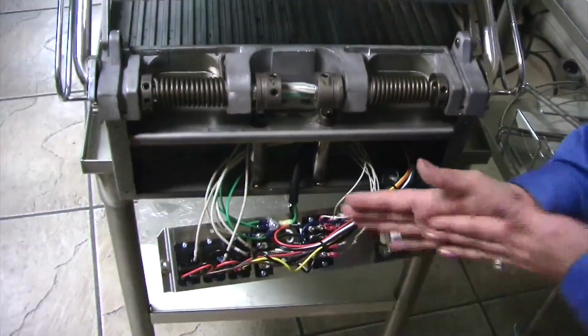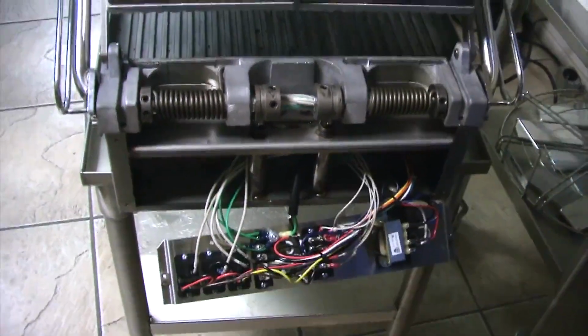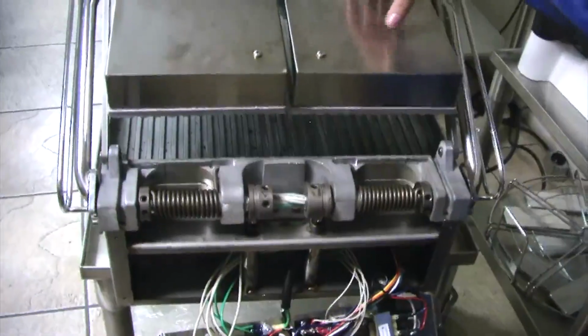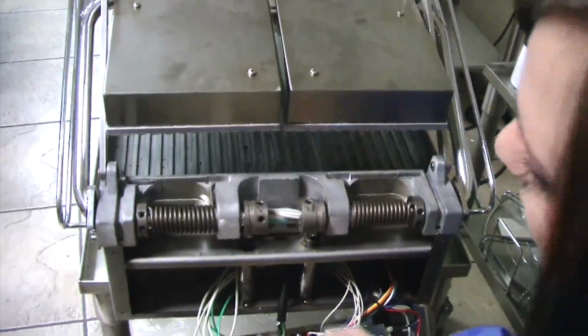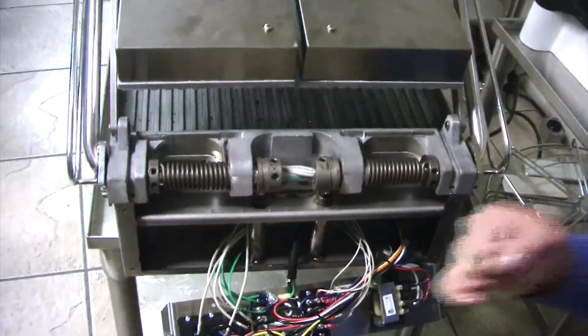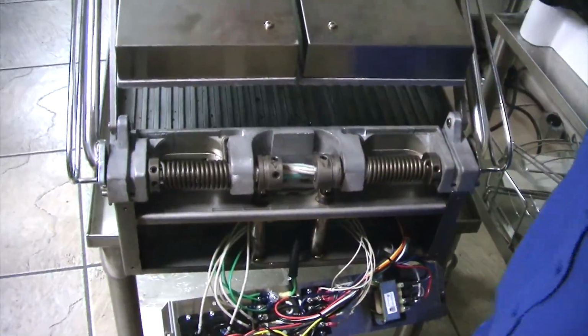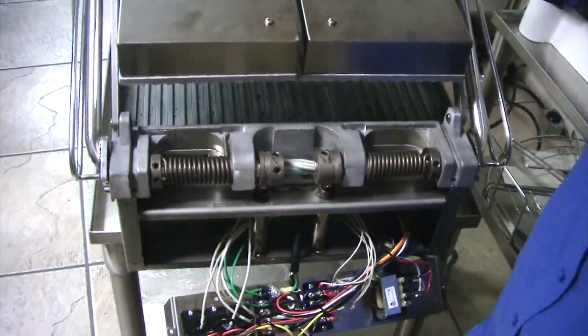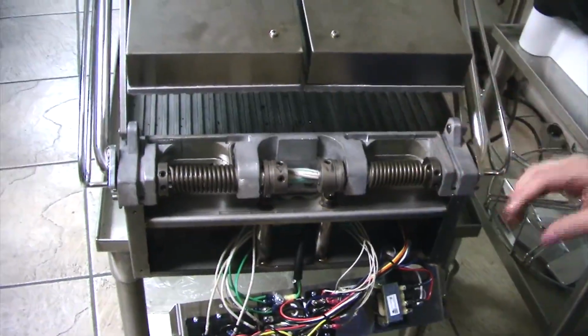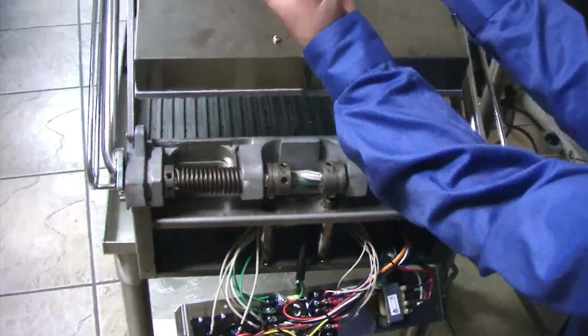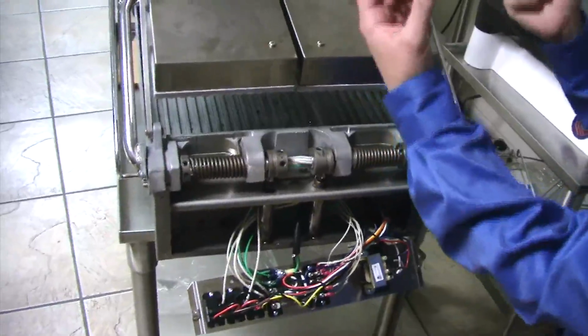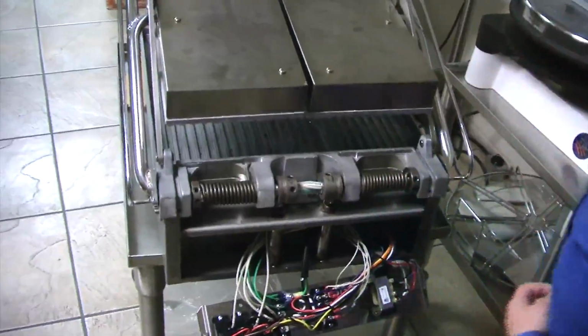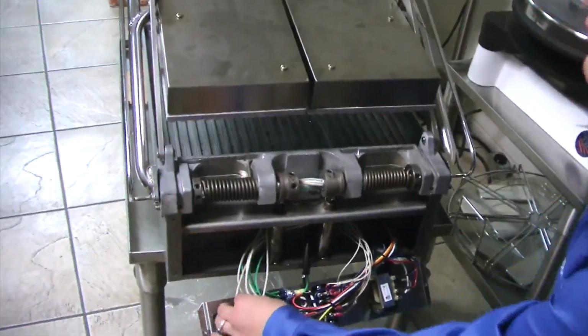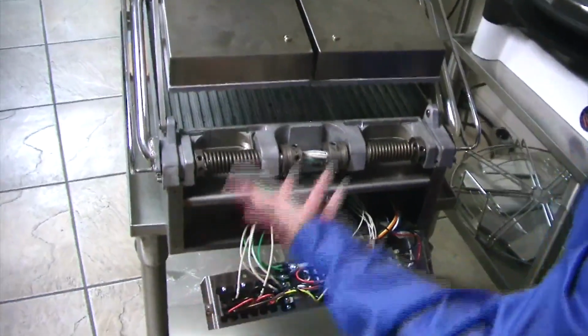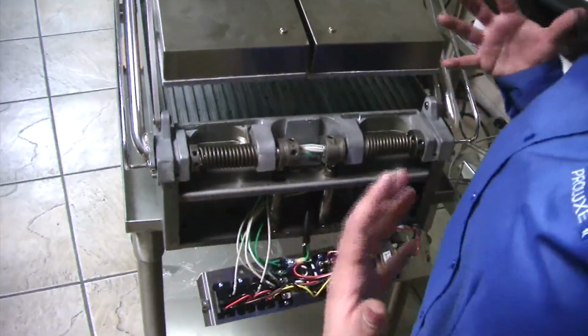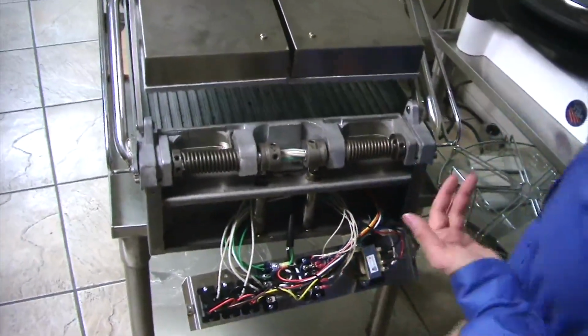Now, you could check these first, I guess. They're probably about 35 ohms for here, so you'd want to check for 35 ohms. You could check here, and if you're not getting the reading, then you definitely want to take it apart and check from the pins of the platen. They are soldered onto the pins. You want to hit directly the two metal pins that come out of the platen, because that'll tell you the real reading of the continuity. If it is giving you the correct readings through the heater wires, then you won't really need to take apart the entire thing to check it. It's making connection to those pins.